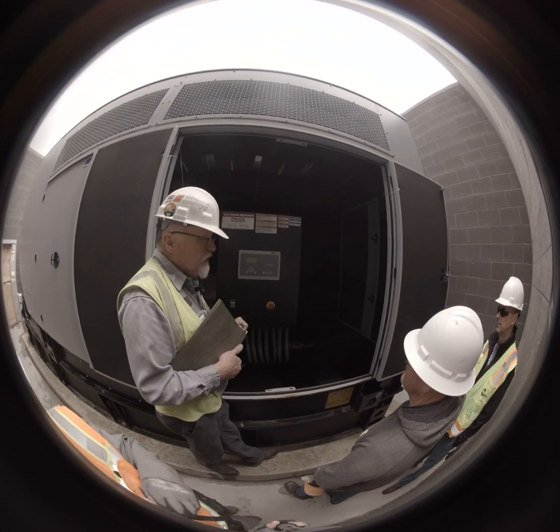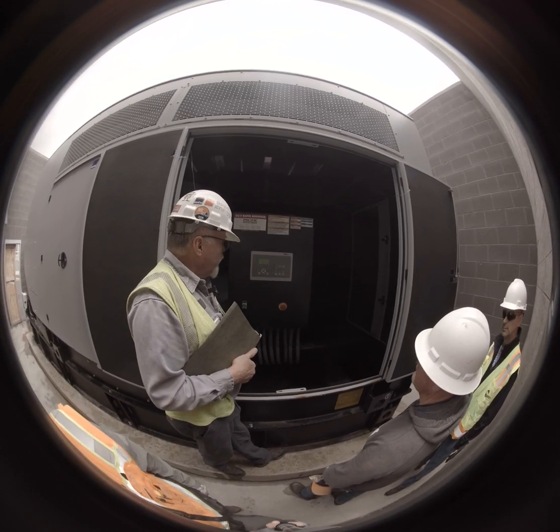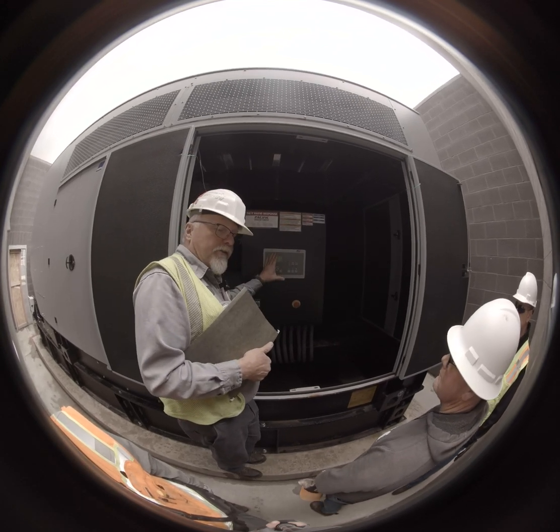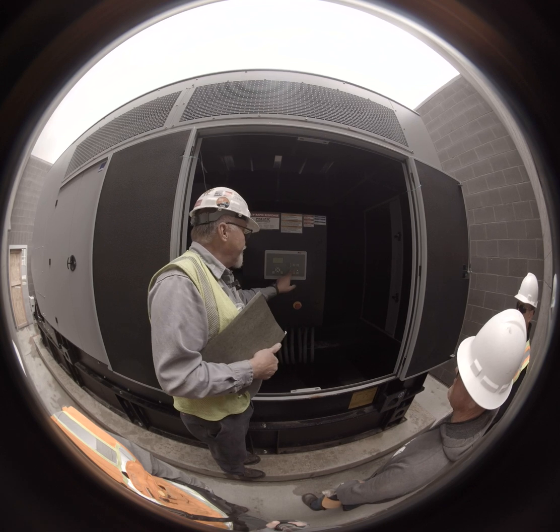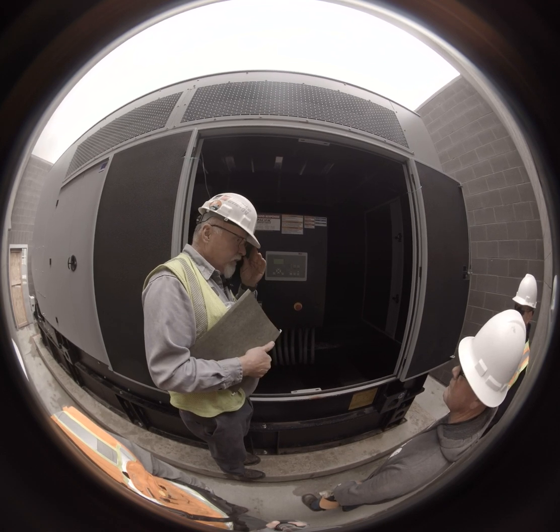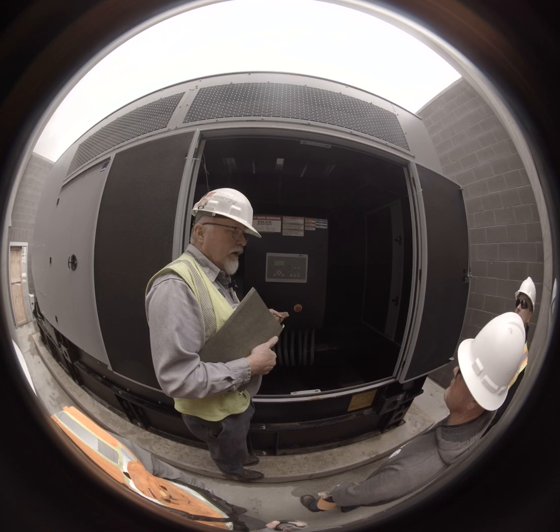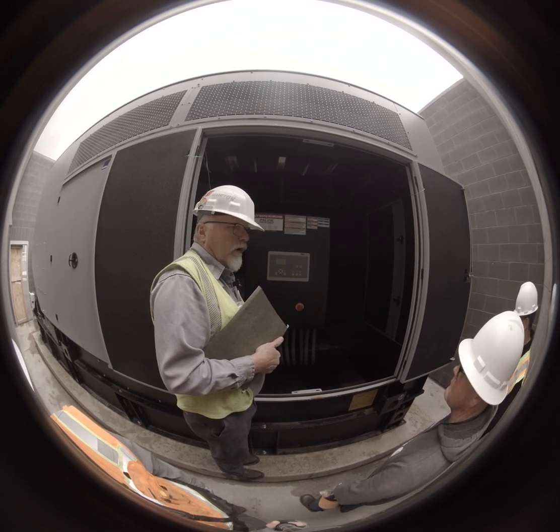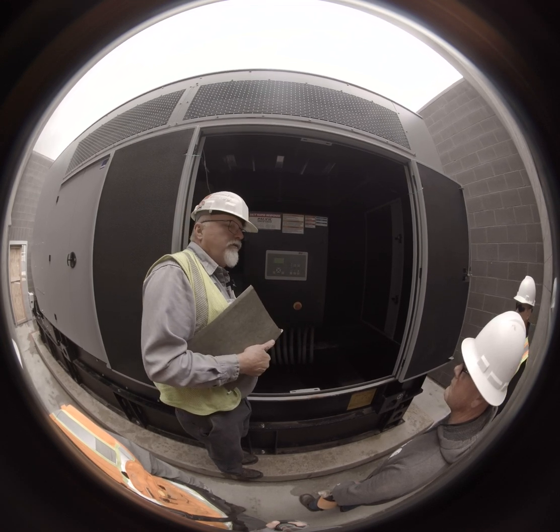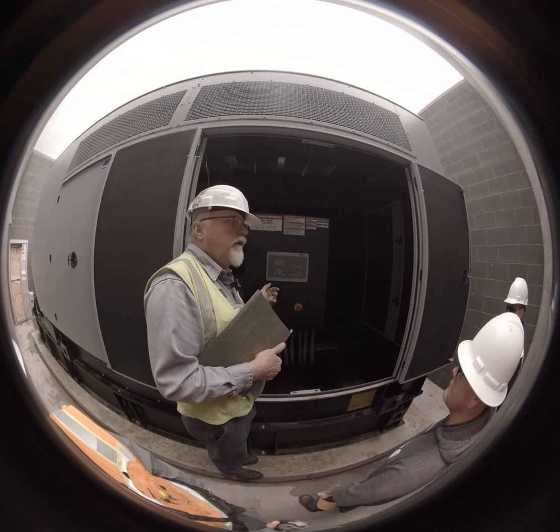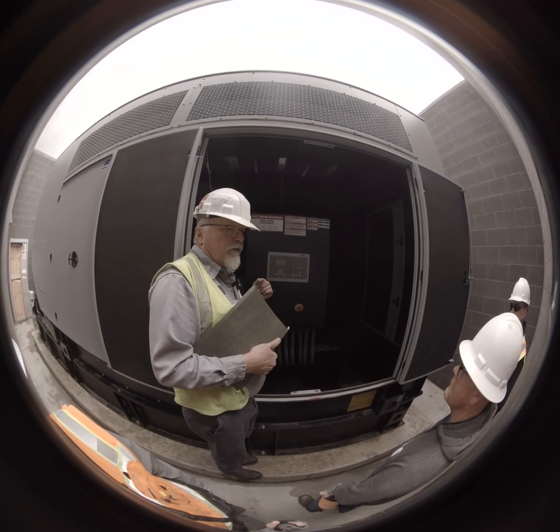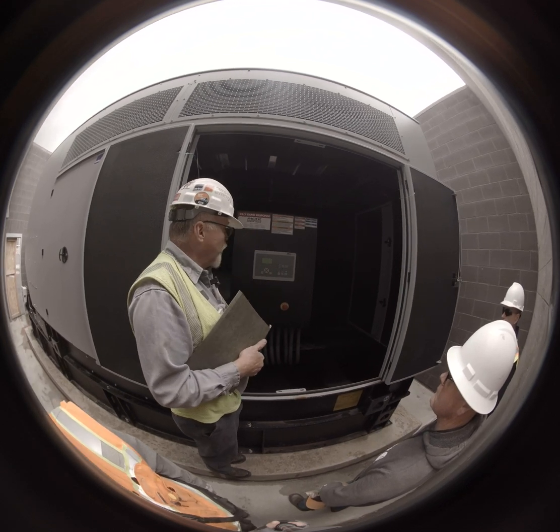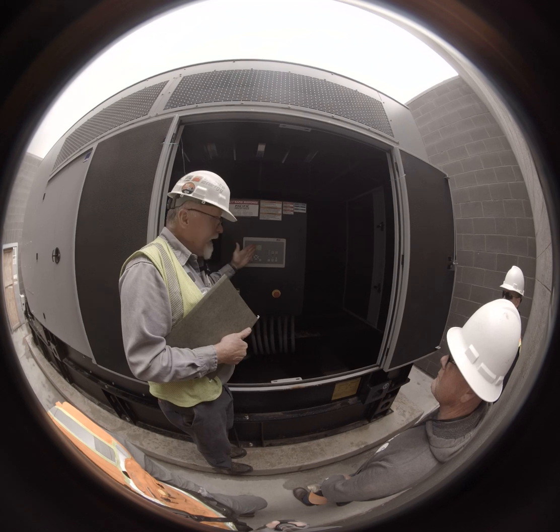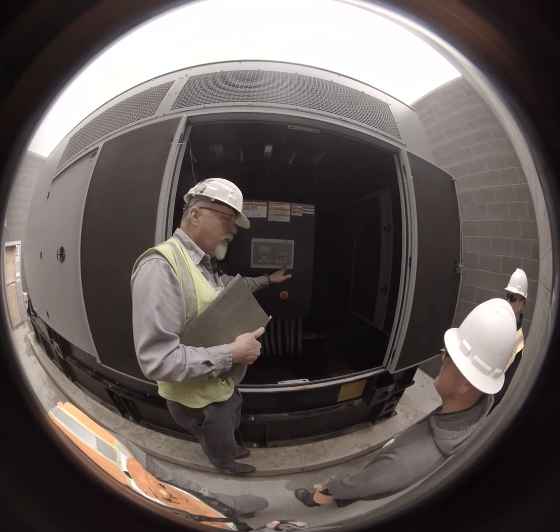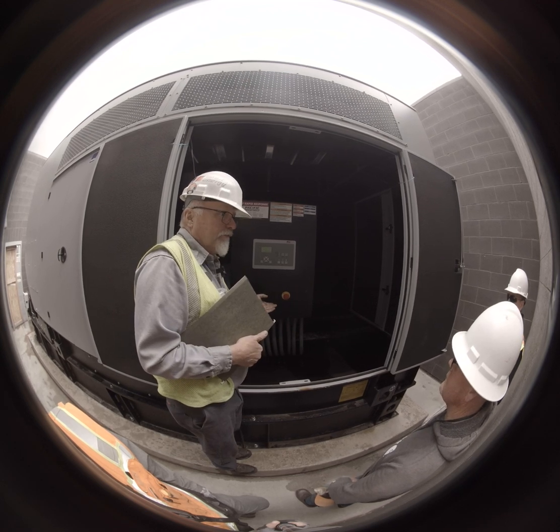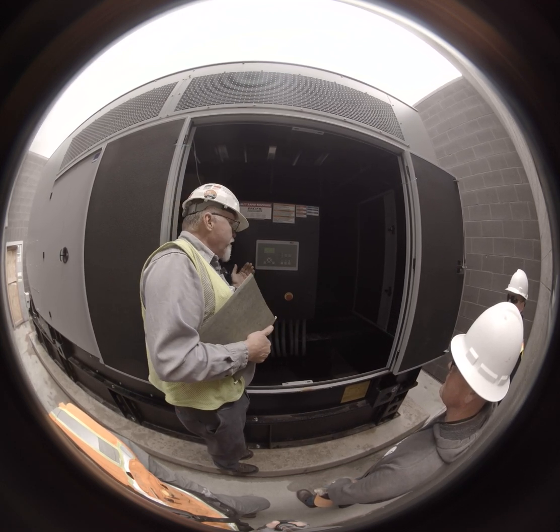Okay, so any questions on any of this? So in a nutshell, short of monitoring what's going on here, you're going to be using this little corner down here. If you do get a shutdown, for whatever it may be, high coolant temp, low oil pressure, or e-stop, that's the number one we'll see, the first thing you always do is clear the reason for that. So if I were to push e-stop right now, the alarm's going to go off. It's going to stay there. We can't get rid of it until we go to the off position here. But if you go back to auto and didn't pull this back out, it's still there. So you have to clear the reason for the fault before you clear the control.